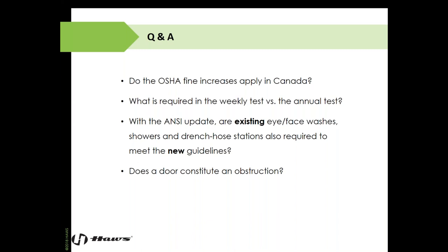Last, does a door constitute an obstruction? This one's a question a lot of people get confused about. Again, a door does constitute an obstruction, with an exception. That door has to meet certain requirements. Again, it has to be non-locking. It has to be push bar or panic bar operated.